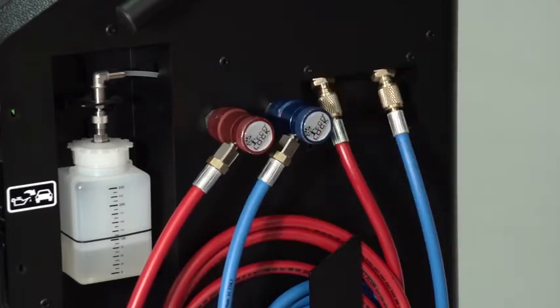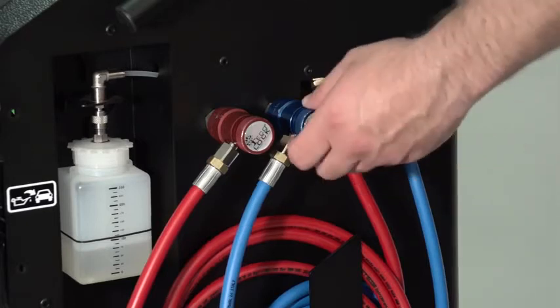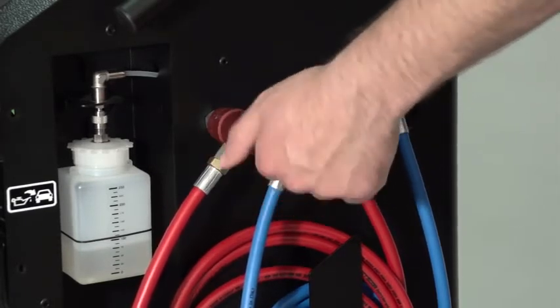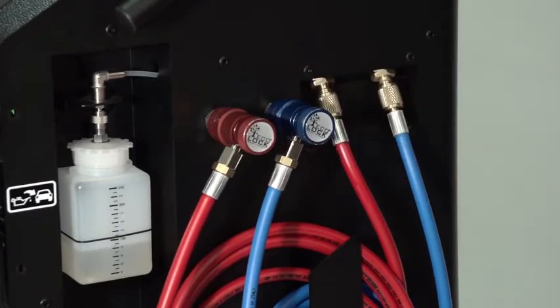Open, continue with your service. At the end of the service, it'll prompt you to close the couplers. Close the couplers. Eco-Lock process will start once you press continue, and it will evacuate that little area again before it allows you to disconnect. It's important that you follow the prompts on the machine with this enabled. With Eco-Lock enabled, it is a roughly 3-minute process each time, so it adds about 6 minutes to the entire service. And Eco-Lock can be disabled in the settings if they choose to.